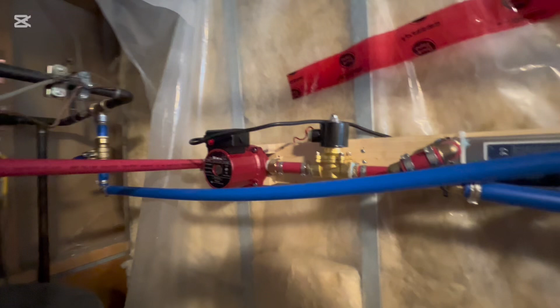So this is the install in the house, and I added a zone valve in here. You can see it on the right, and also a valve to regulate the flow. That zone valve operates on 110, and it'll shut the water flow off from the hot water tank as soon as the system isn't operational. The other valve regulates the flow going back into the hot water tank so I can achieve maximum heat transfer in that heat exchanger.